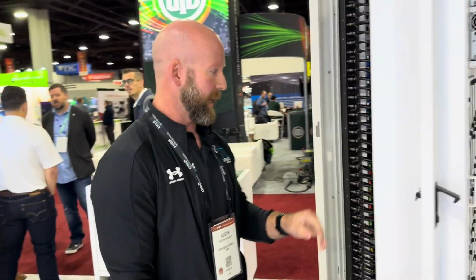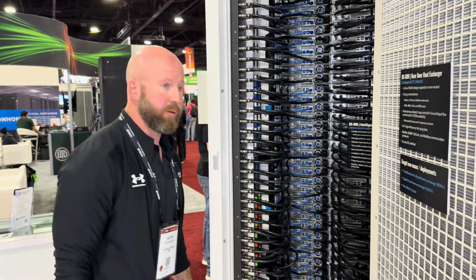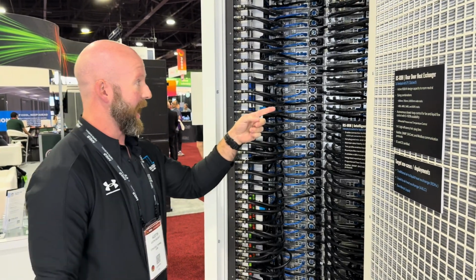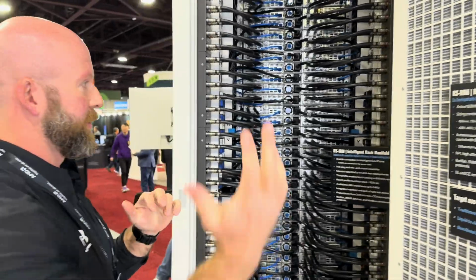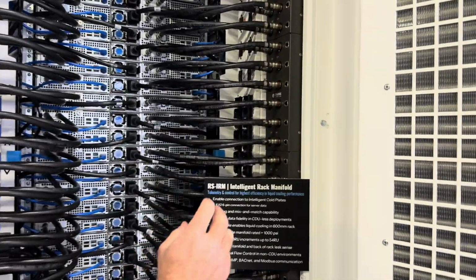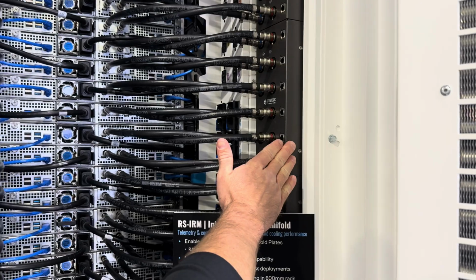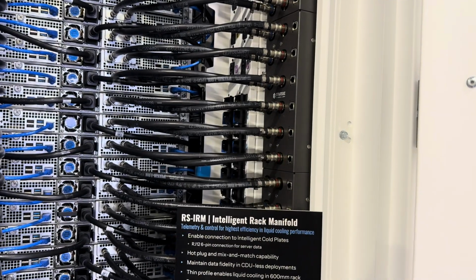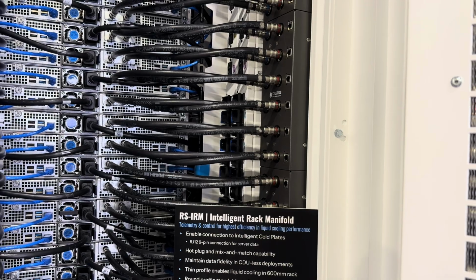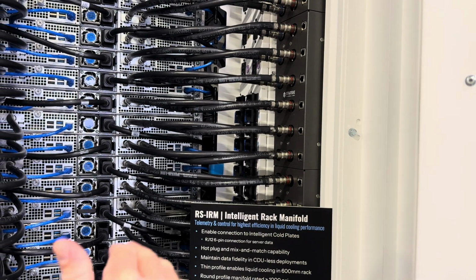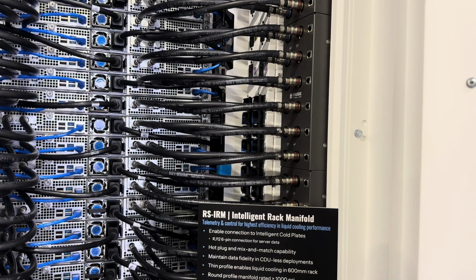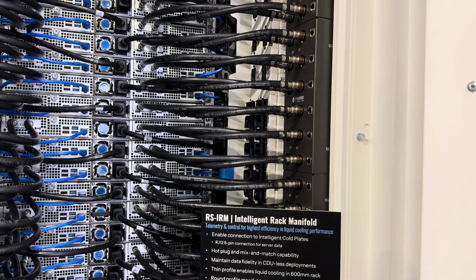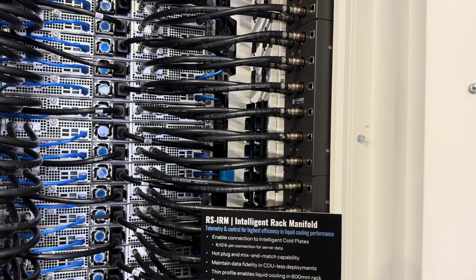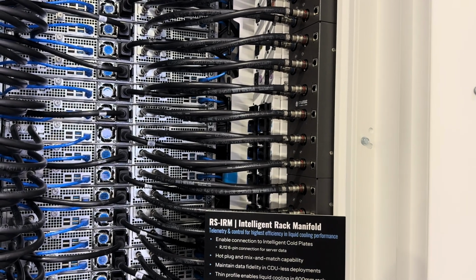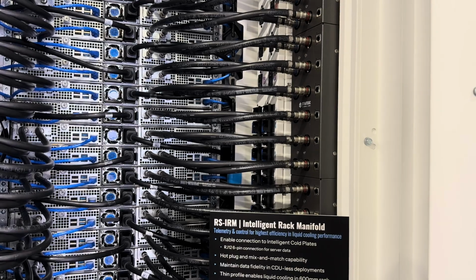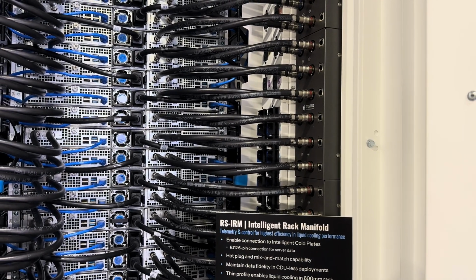All right, if you'll follow me into the back of the rack, next up I'm going to show you our intelligent rack manifold. That's what you see back here. If you want to zoom in a little bit here, we have a circuit board that sits underneath this bezel, and you can see our RJ12 connections on there. This allows us to collect liquid telemetry from each one of the servers that are currently being handled by the manifold in the back of the rack. So we can collect information like inlet temperature, outlet temperature, case temperature of the cold plate, leak status, and push that information back up to our top of rack controller and use that to make decisions on flow rates that are allowed to go through the manifold.